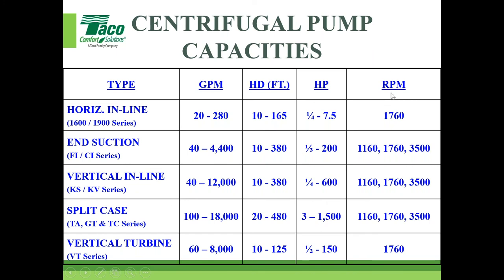But nonetheless, it gives you an idea of some of the ranges that are available here. For the most part, I think we all can agree that in the U.S., 1760 is the normal speed. There are 3500s offered out there. Motor pricing probably is going to be a challenge. Same thing with the 1160s. Replacements will be a little higher. And the faster you spin the pump, the quicker it's going to wear out. So that's something to be considered. 1160s have their use, but most of the pumps we send out are 1760.